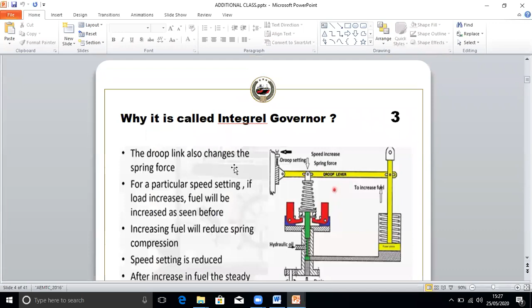And we know that for both generators to share the load, they should have a common intersecting point. That means the droop should be the same. If the droop is not the same, the kW load sharing will be different. One generator will take more kW load, one will take less load. When the droop is the same, the fuel you are giving is exactly the same to both engines, so the kW load is the same. Whenever you increase or decrease fuel on one side, you are giving one engine more torque and one less torque, so that one will take more load.